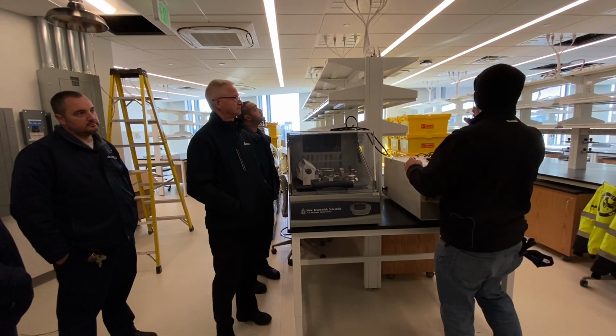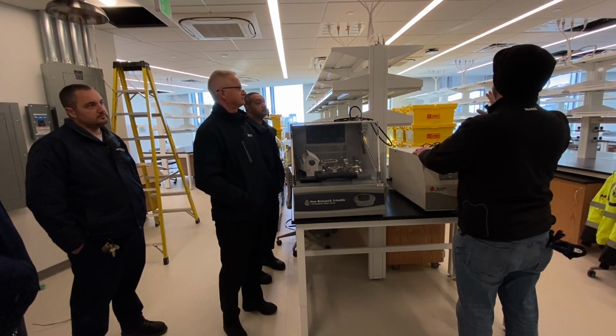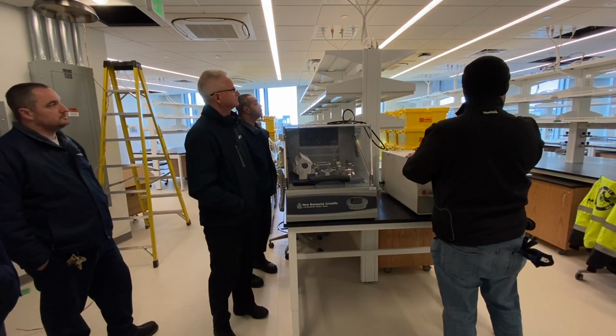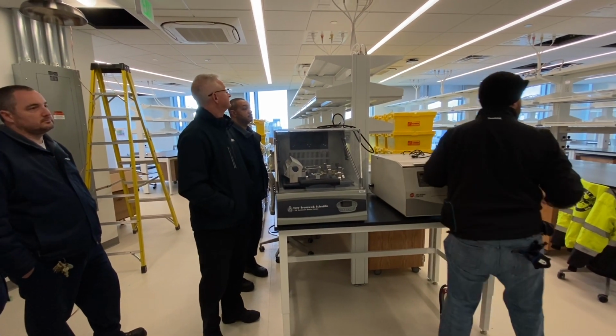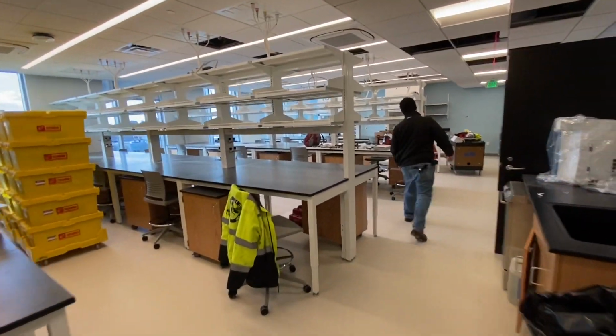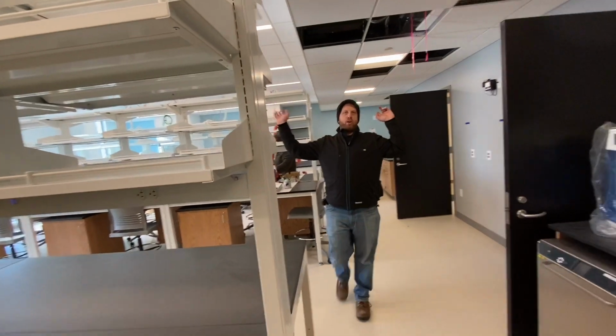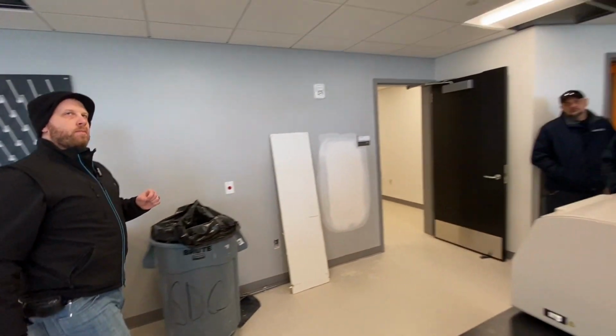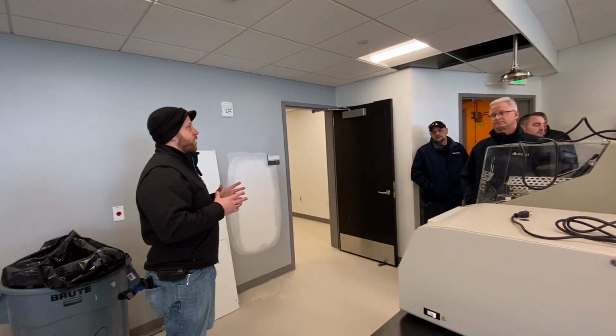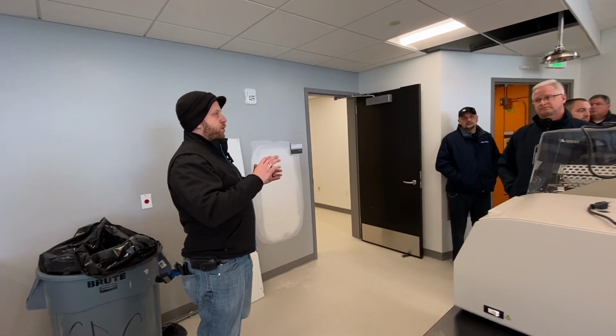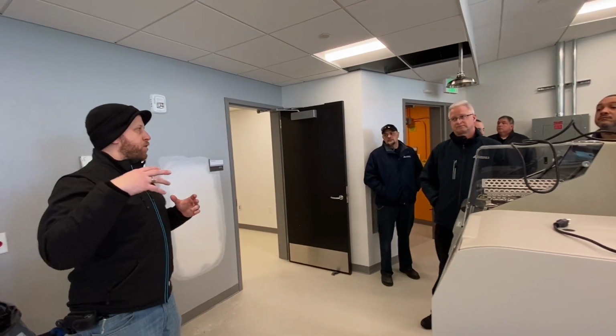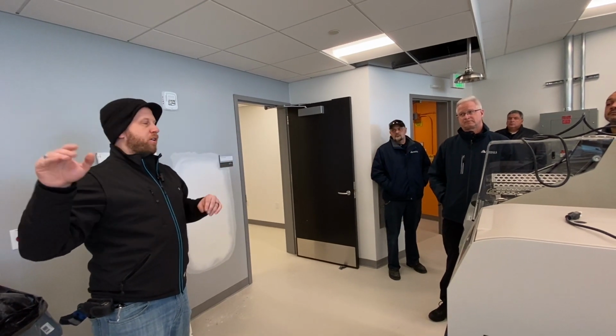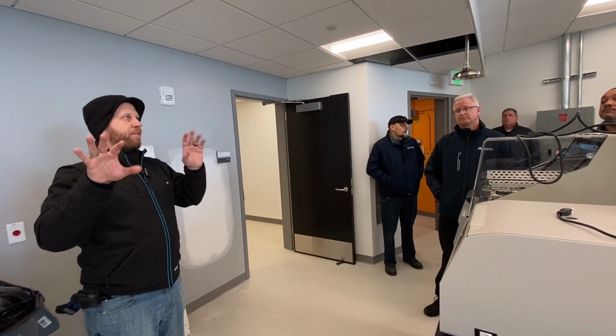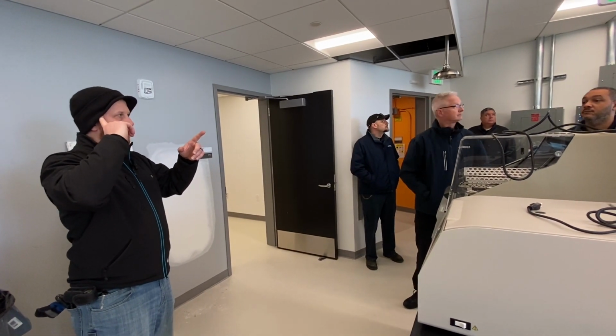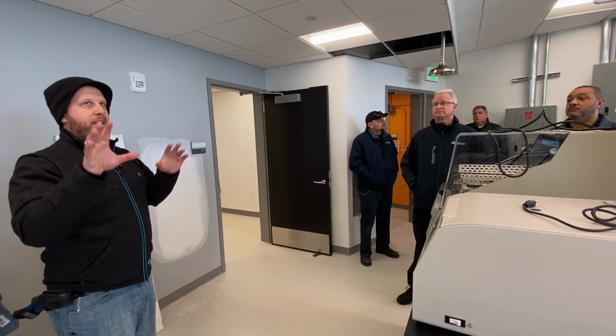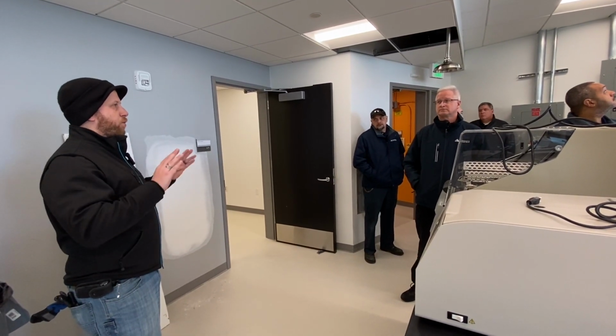So these wet labs will have this one, I think this is the smallest one. This one has 4 or 5 head units and one thermostat, which I think is on this wall over here, but there's one thermostat that pretty much controls all these head units. In the BMS system you'll see what we call leader-followers: you have one where the thermostat's wired to, which then tells all the other head units to also be in the same condition. Some of them may have different filters, so if one hasn't had a filter changed or cleaned in a while, they can have their own individual alarms, but mostly they all control off of one room thermostat.